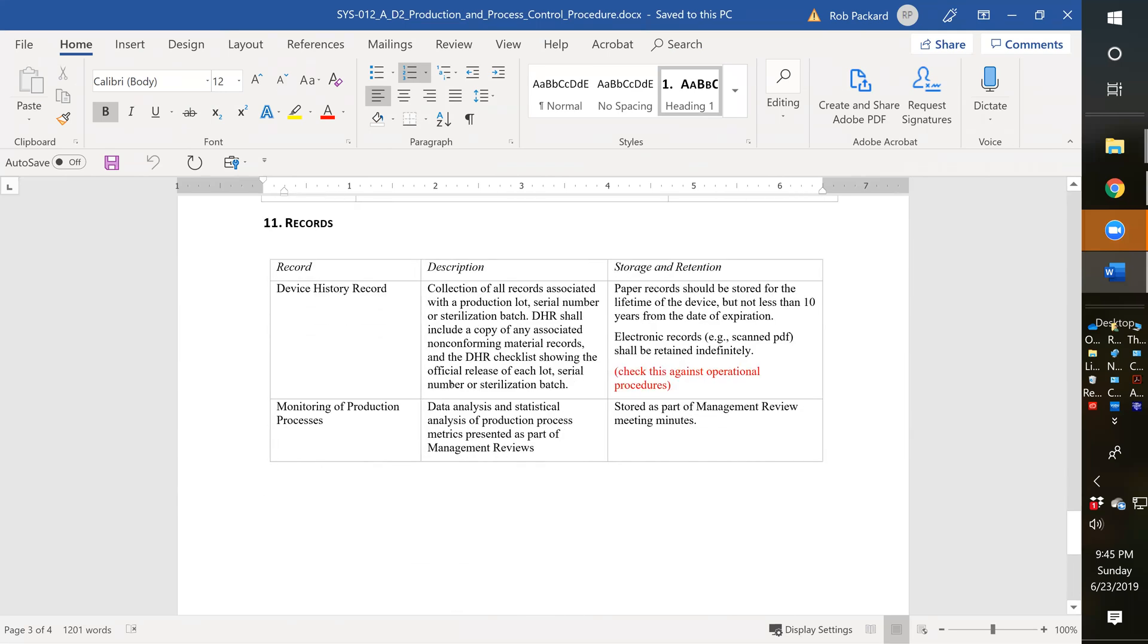And then down below here, we have records. You have a device history record as one of your records from any manufacturing production process control procedure. We talk about paper records and electronic records, and what should be in those records. We also include the requirement that nonconforming material records, copies of them should be in the DHR. And you should have the DHR checklist for release also included. So that's what's included in our procedure.